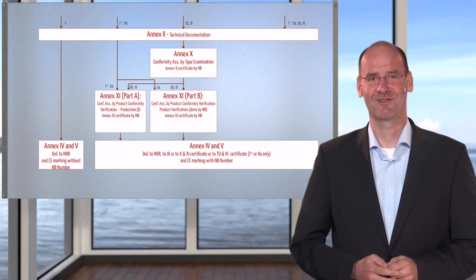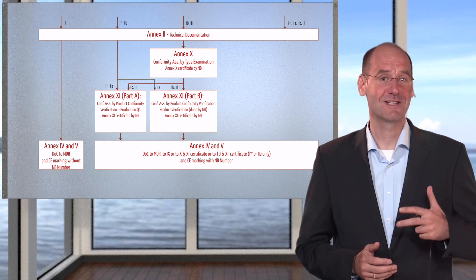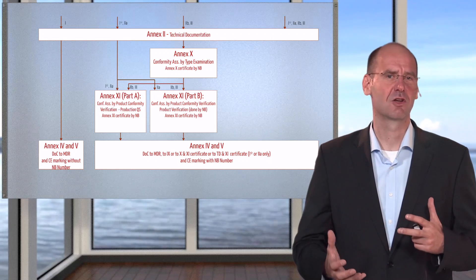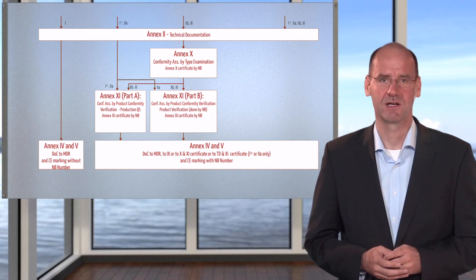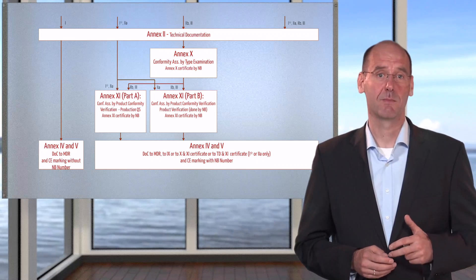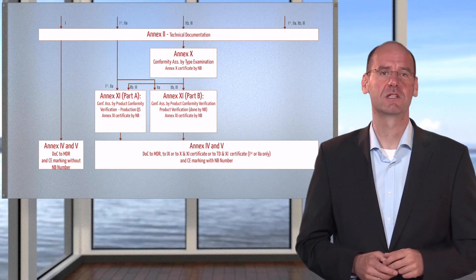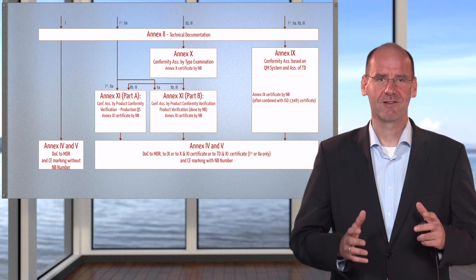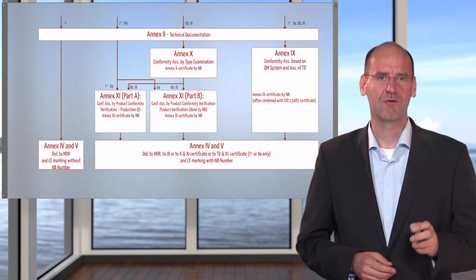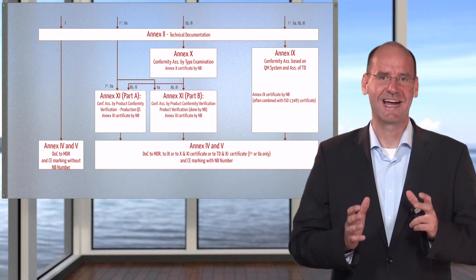However, for medical devices containing software, you cannot ignore the development. It is hard, if not even impossible, to find problems by testing the product alone. Therefore, the audit of the quality management system must include the development as well. And then we are at Annex 9. Annex 9 describes a full-blown quality management system, including development, including production, and all other processes such as post-market surveillance, risk management, etc. And honestly speaking, if your product contains software or is software, you should go this Annex 9 route — at least if your product does not fall in class 1.